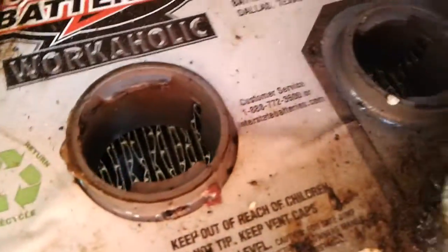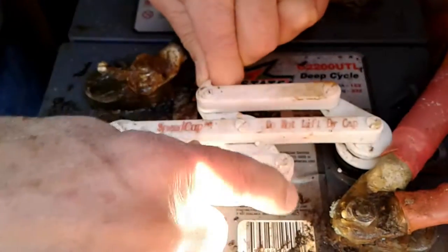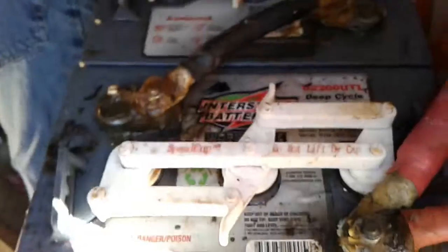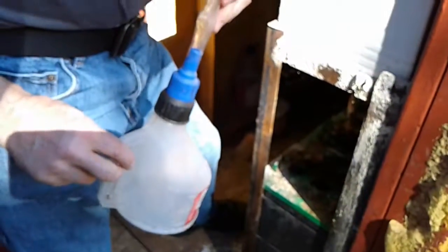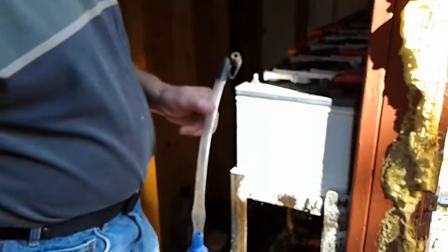These are really low, so we're going to have to get some. Okay. I think we've got some, and it's distilled water. And we usually have it in there, but okay. And so you need to go through and check each one and fill them. The way I fill them, I just have this thing here. The biggest problem you have is knowing when they're full without them flowing all over the place. Uh-huh. And so this allows you to be a little more specific. Yeah. Filling them up. And so today, sometime, I'm pretty sure we've got some water, and so these all need to be filled, and that only has to happen once a year. Okay.